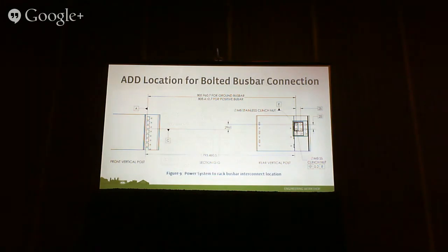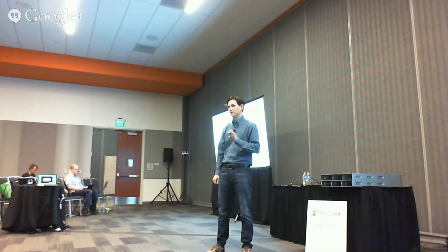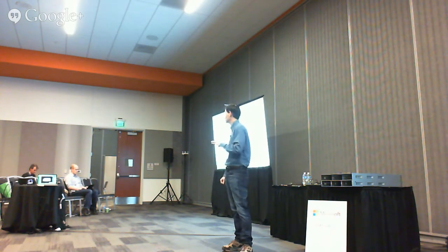This is something we started talking about last year. It identifies the location for a voltage connection between the power shelf, like what we see here, and the bus bars sitting in the back of Open Rack. We'll look at the text in a second, but we start with a minimum of 2 voltage connections, scaling up to 4, then 6, then 9. Depending on the power a customer wants to populate the rack with, or the power density you're working with, you can increase or decrease the number of voltage connections on the rack.